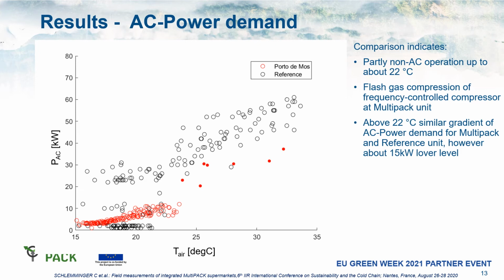By comparing the AC power demand of the MultiPACK and the reference side, we noticed two differences. There is much lower AC power demand for both sides below 22 degrees ambient temperature. Based on the nature of the CO2 as a working fluid, we see that there's a small power demand also below 22 degrees C in order to handle flash gas from the evaporation.